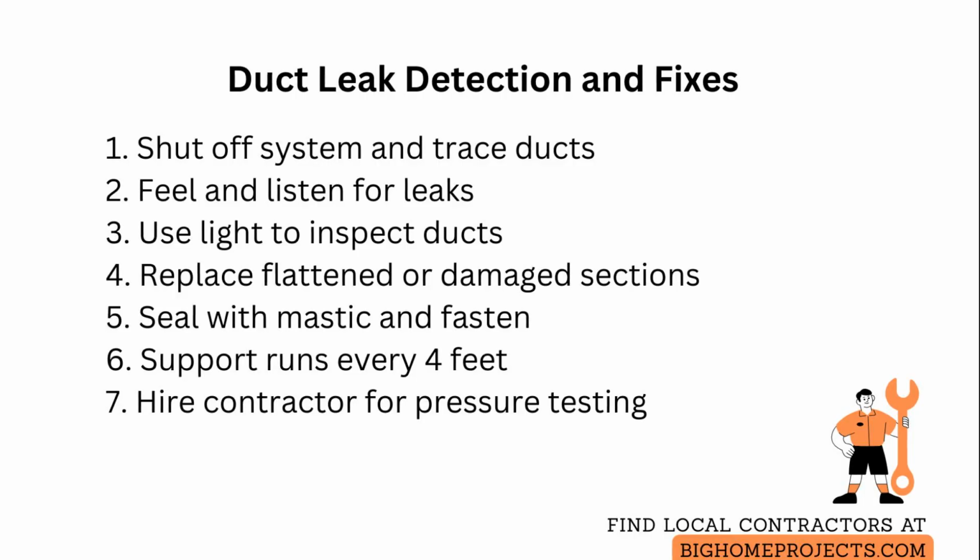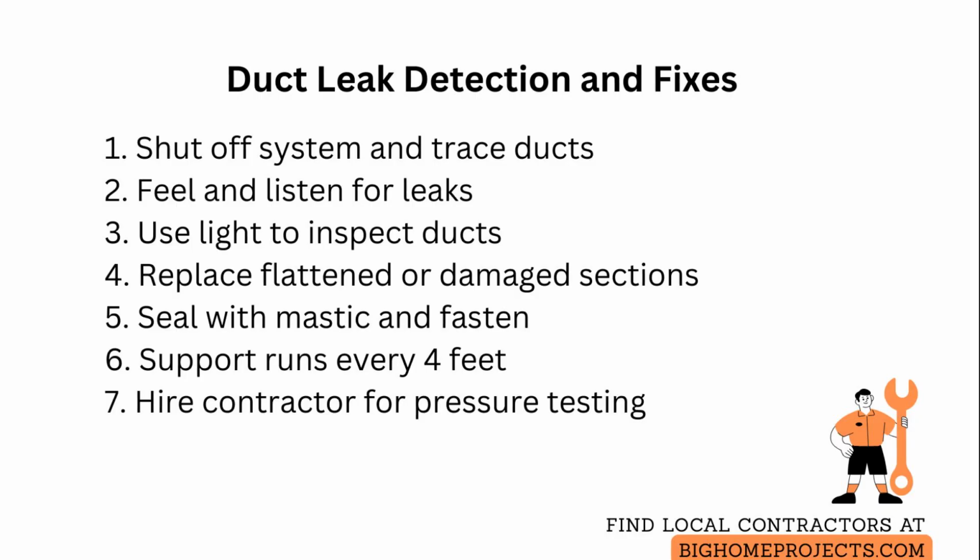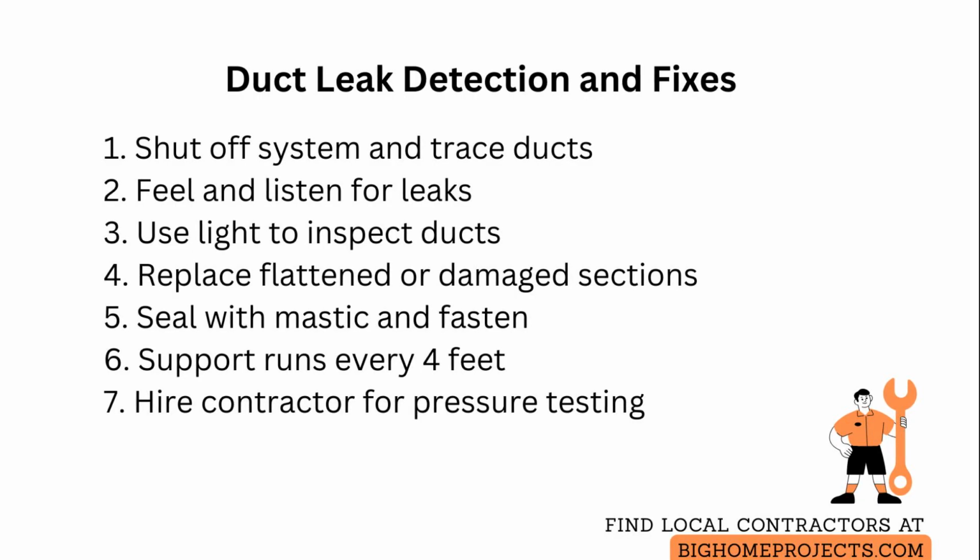When access is limited, consider hiring a contractor who can perform a pressure test with a duct blaster to quantify leakage and locate problematic sections with a smoke pencil or infrared camera for hidden breaches.